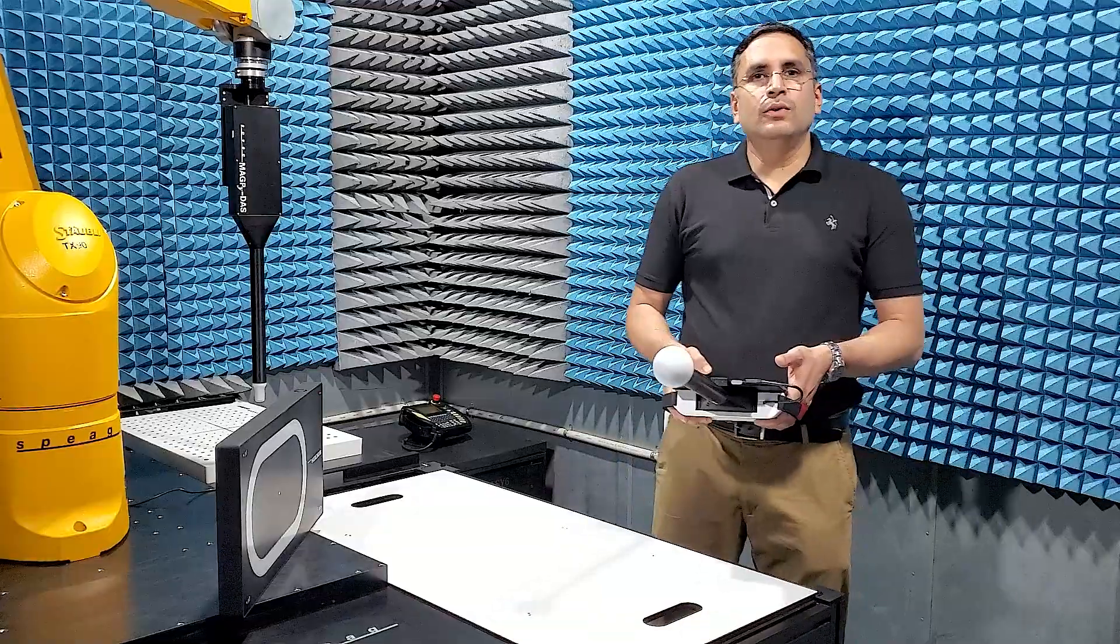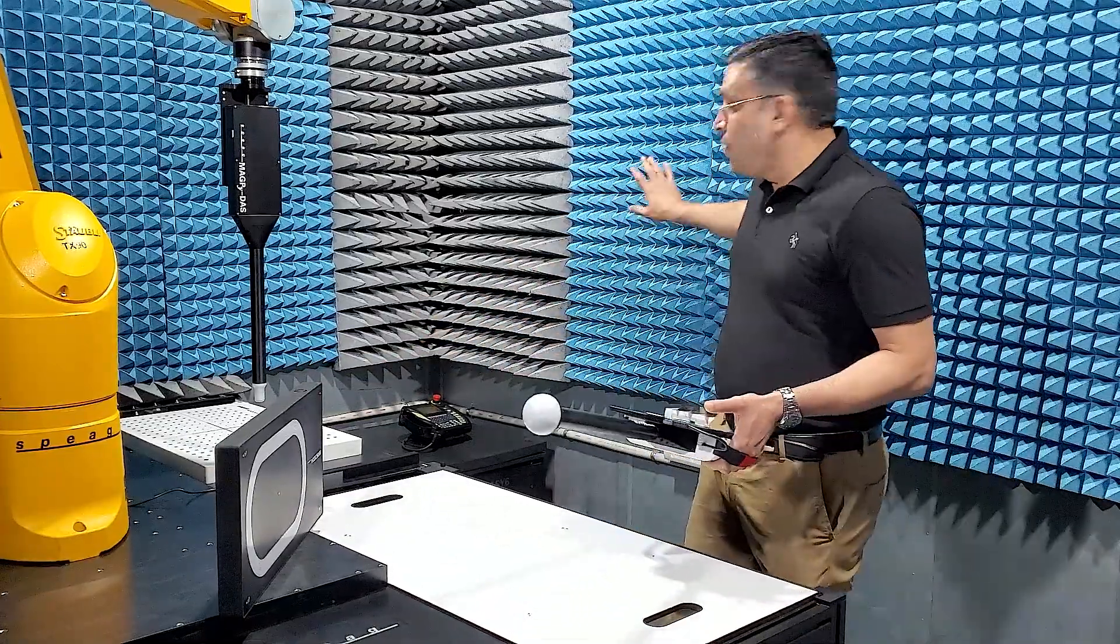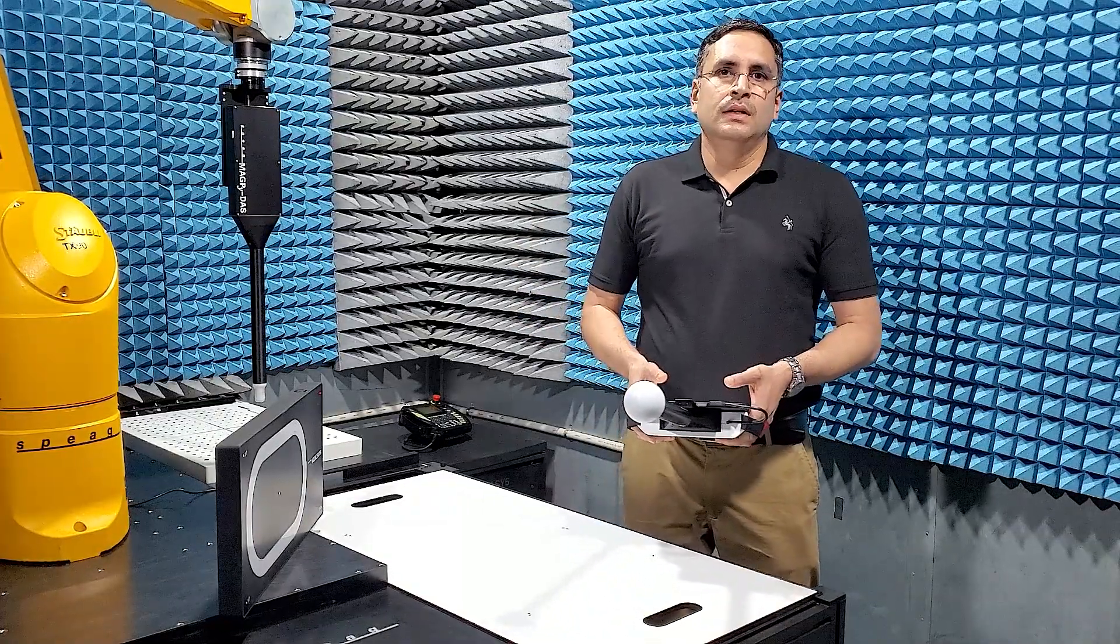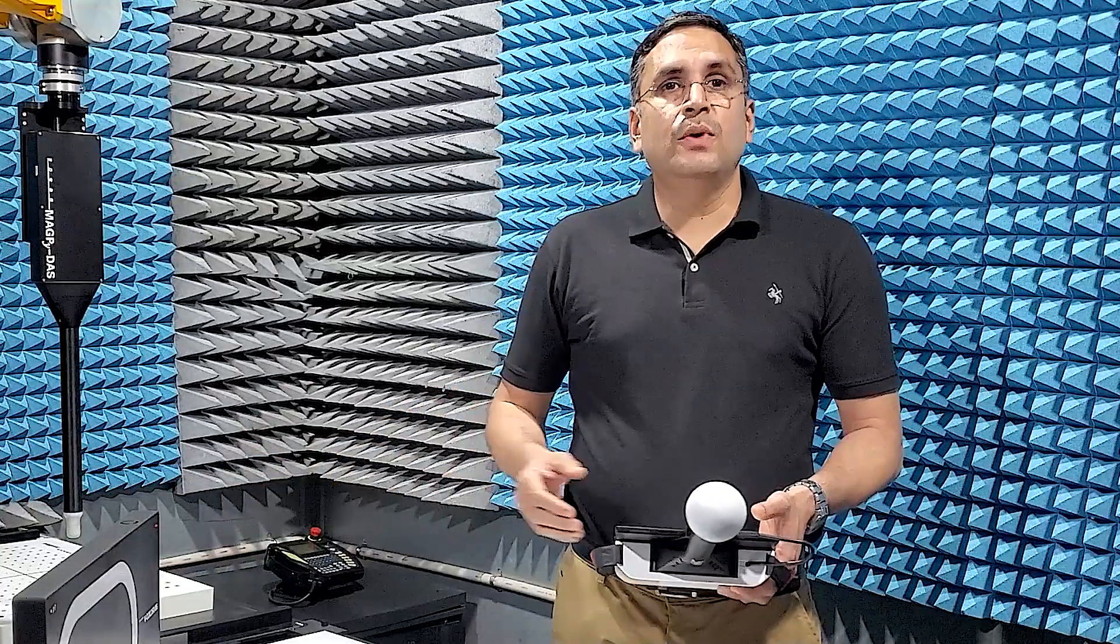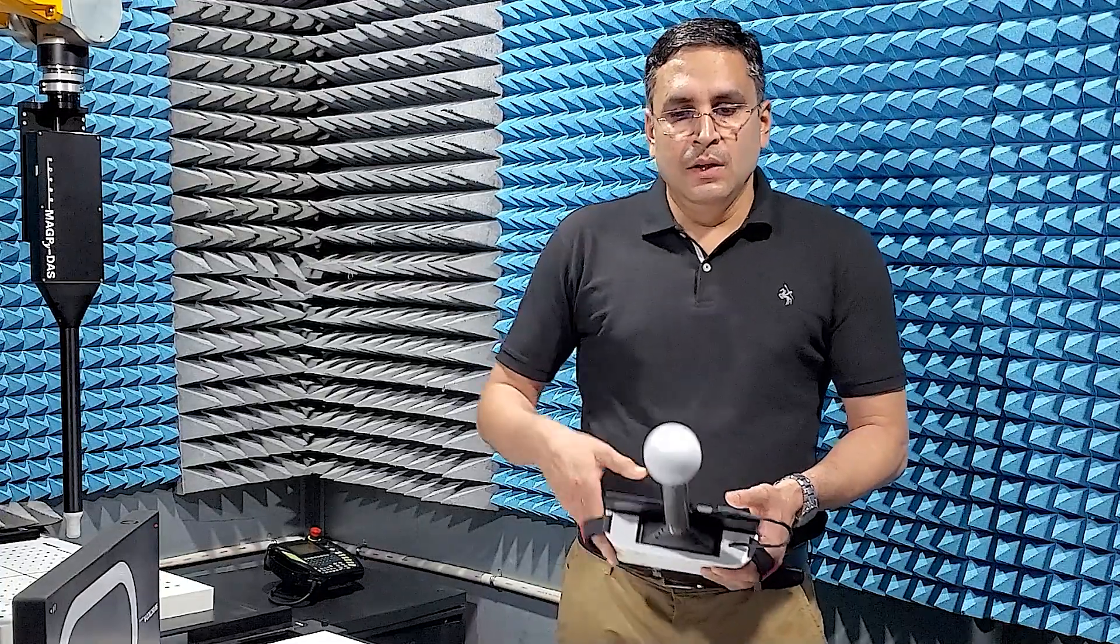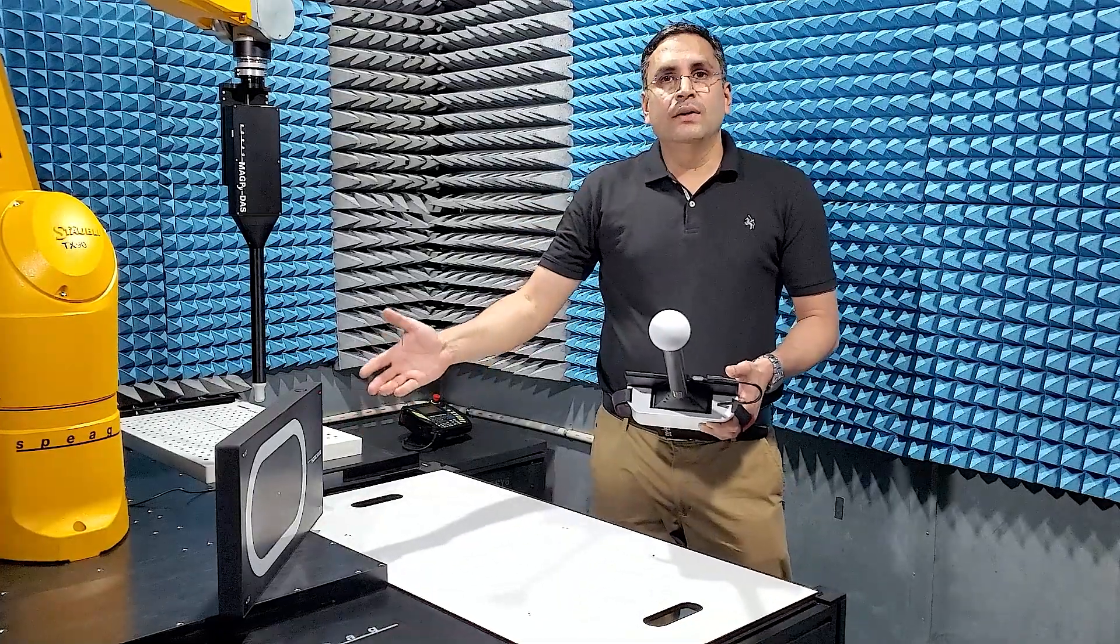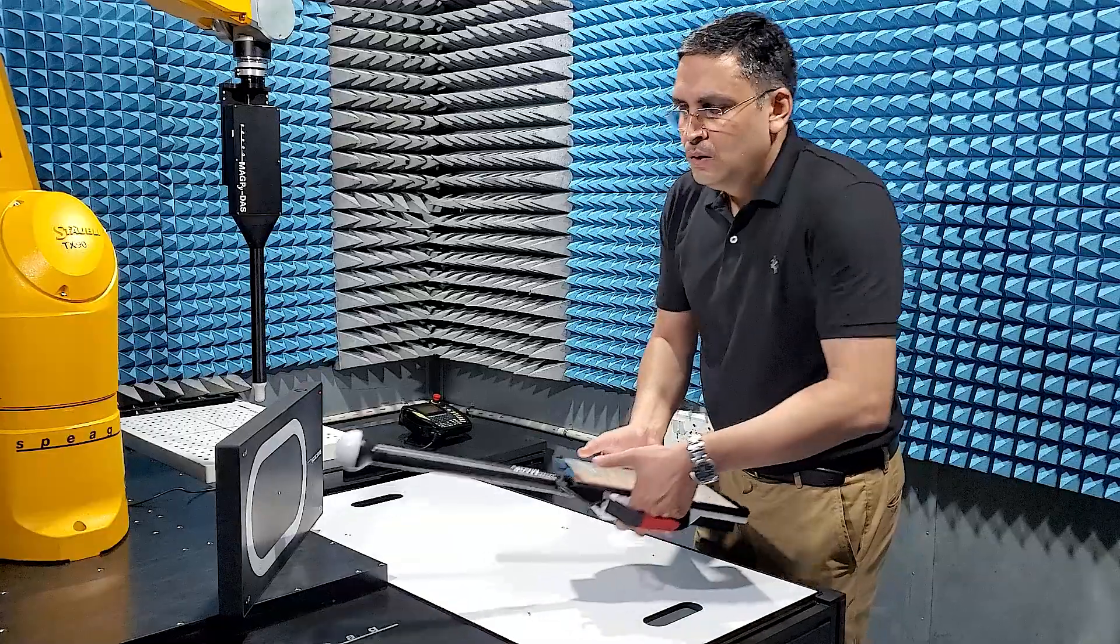Just for fun, I want to determine the safety or compliance boundary of this validation source, assuming it is mounted to the wall. That's all pretty straightforward. The only thing that is not so intuitive is that the device evaluates the exposure in a well-defined orientation with respect to the exposed body. This means that the probe estimates the induced fields for fields penetrating the body in the direction of the probe axis. For this coil mounted at the wall, the probe is oriented horizontally like this.